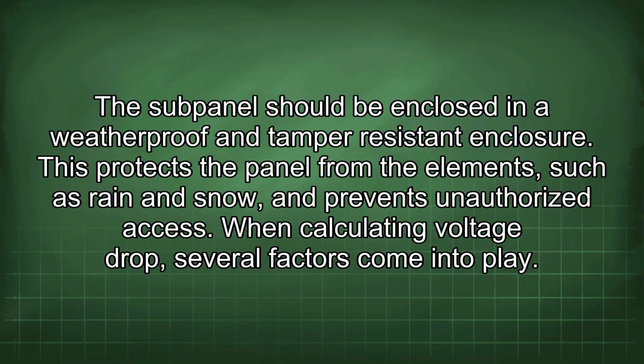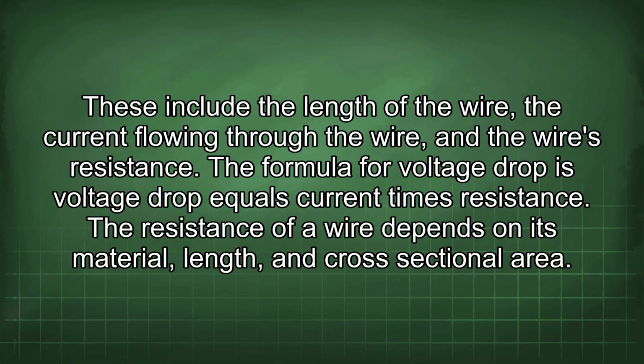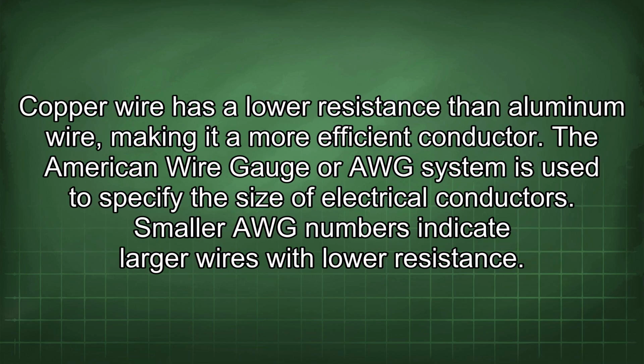When calculating voltage drop, several factors come into play. These include the length of the wire, the current flowing through the wire, and the wire's resistance. The formula for voltage drop is voltage drop equals current times resistance. The resistance of a wire depends on its material, length, and cross-sectional area. Copper wire has a lower resistance than aluminum wire, making it a more efficient conductor.